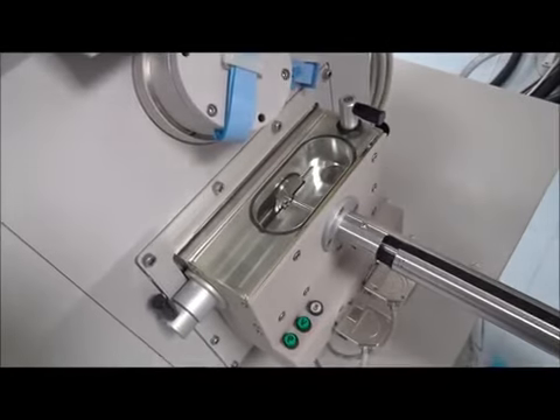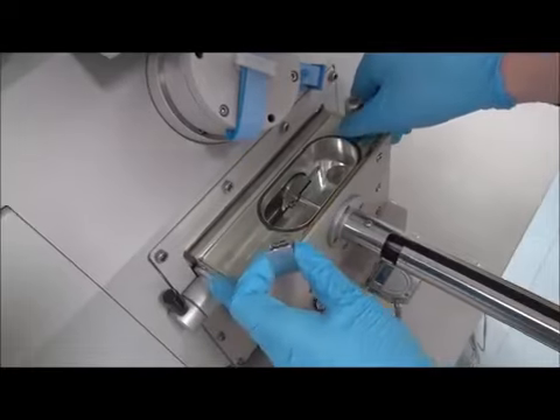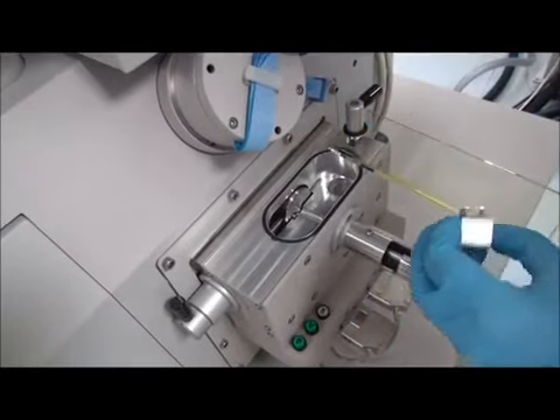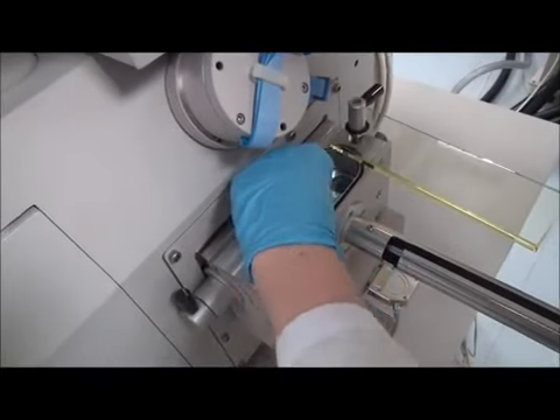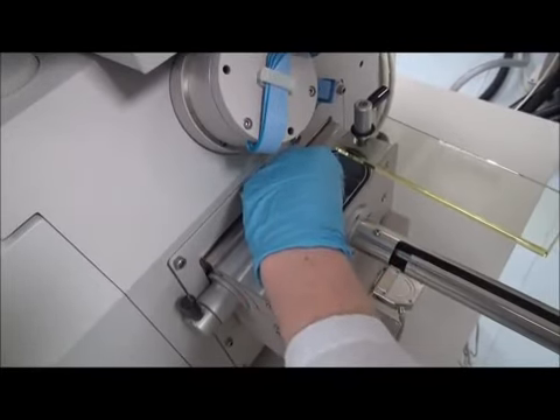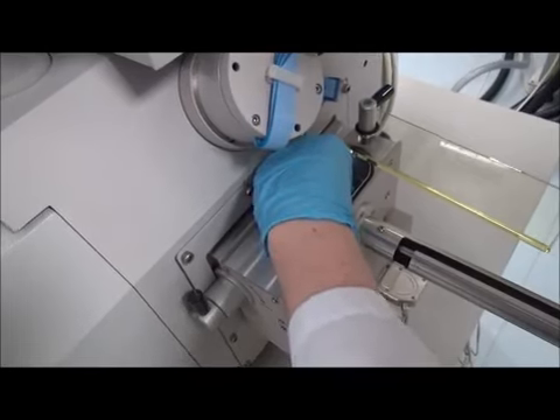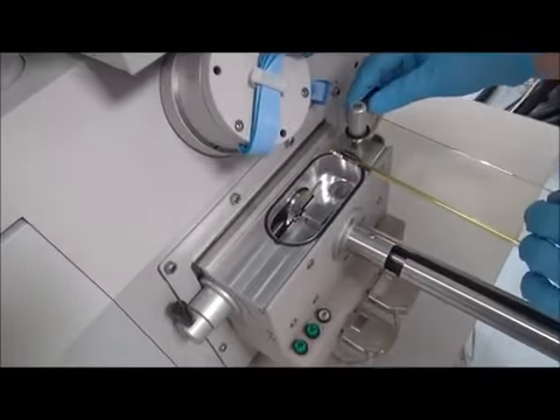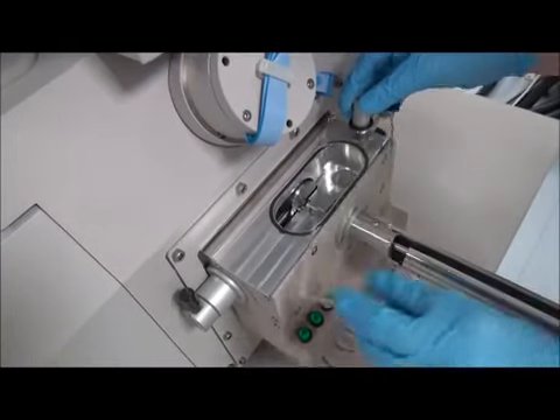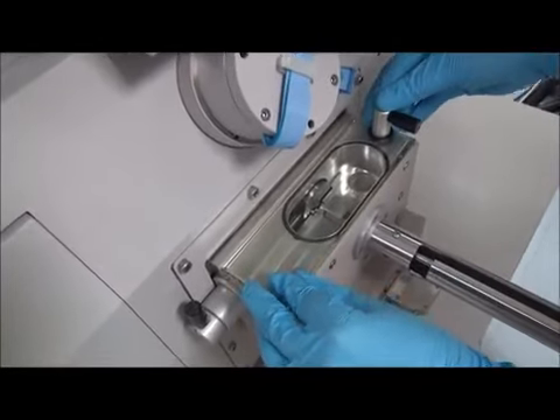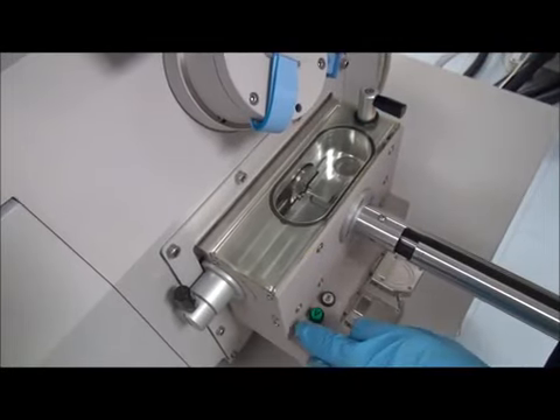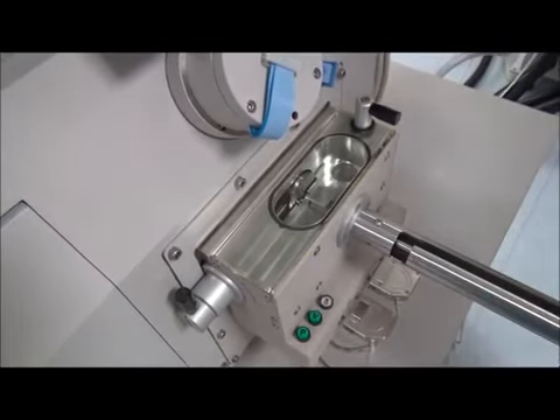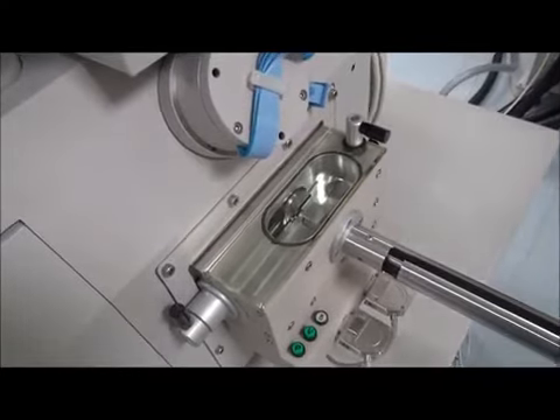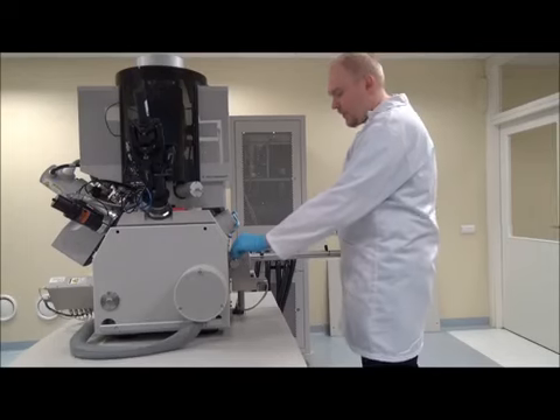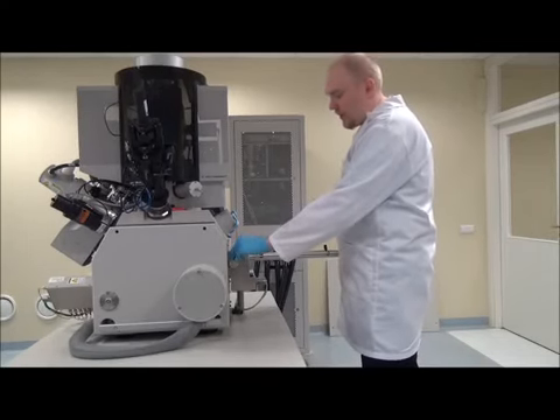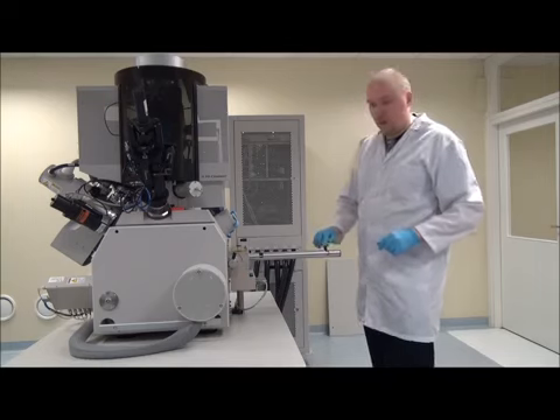The airlock was previously ventilated, so I can simply open it now. And I will put in the sample. As you can see, the sample is fixed inside, so I will close it. And now I will pump out the gas. So I have pumped out the gas, and now I have to put the sample inside the chamber, and I will do it with the help of this rod over here.